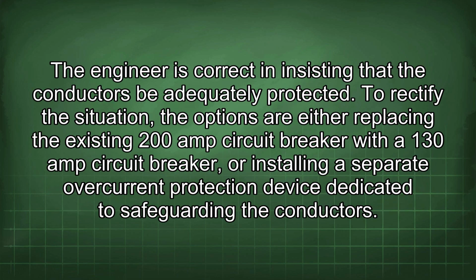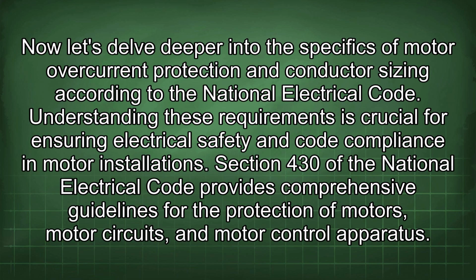The engineer is correct in insisting that the conductors be adequately protected. To rectify the situation, the options are either replacing the existing 200 amp circuit breaker with the 130 amp circuit breaker or installing a separate overcurrent protection device dedicated to safeguarding the conductors. Now let's delve deeper into the specifics of motor overcurrent protection and conductor sizing according to the National Electrical Code. Understanding these requirements is crucial for ensuring electrical safety and code compliance in motor installations.